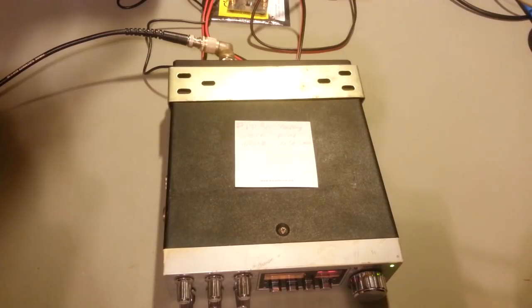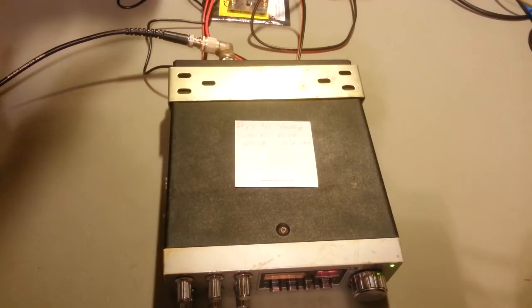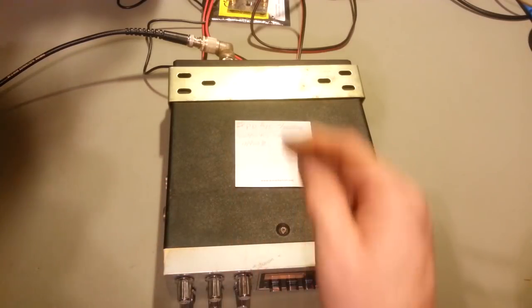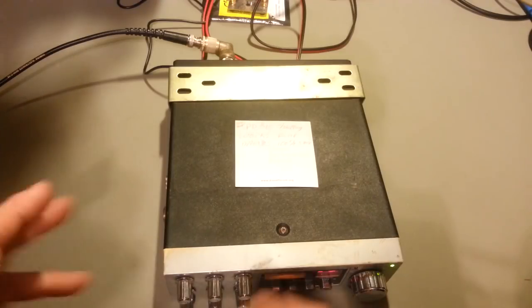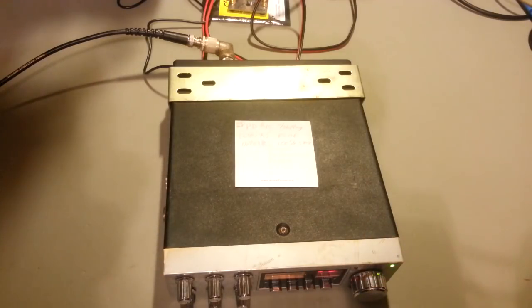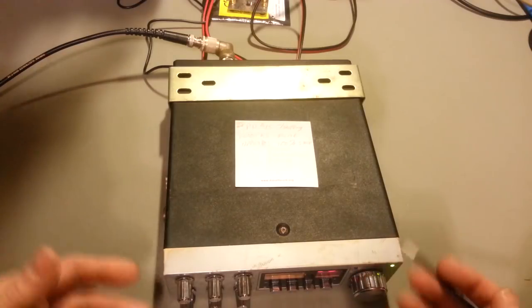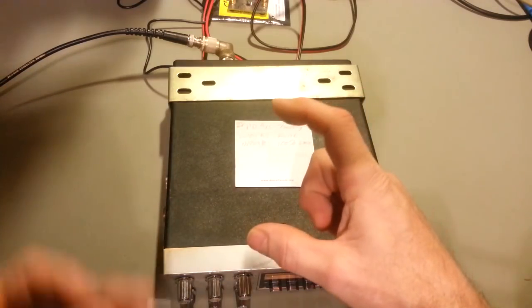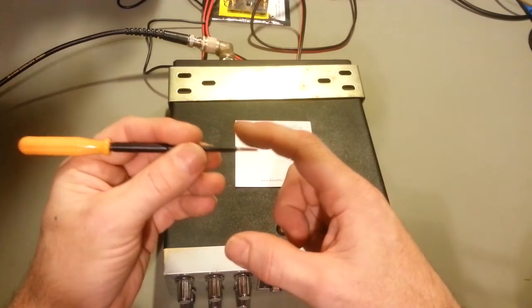They were giving SINAD measurements with 100% modulation, because they said, well, the 30%, you don't talk at 30%. You're going to be talking more at 100% modulation. No, you're not. The reason they pick 30% modulation, and actually I can do that with this communications test set, I can take power measurements over time, okay? But that's the problem.